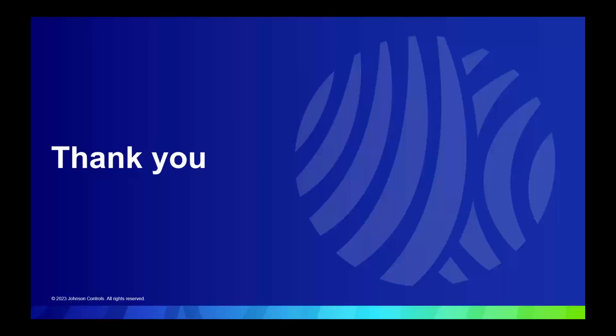One good thing, Troy, in case you're not aware, about 2.5 years ago we launched a new nozzle called the 9.5W nozzle. It's a wide angle nozzle that's good from 6 to 18 inches, and at 18 inches it has approximately a 50-inch spray pattern. So for very limited, tight areas, that nozzle is available. One main design guidance is that it needs to be a minimum of 6 inches away from any superheated surface, so we don't have issues with the nozzle cap.